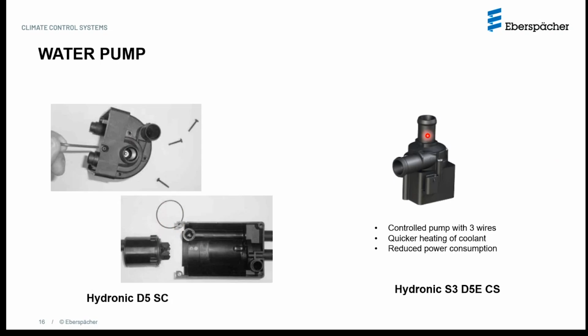Unfortunately, the coolant pumps on the Hydronic S3 are non-serviceable in the sense that you don't have any replacement part, especially the O-ring is not available as a replacement part. So in case you have a bad pump, which is highly unlikely, then you will have to replace the entire pump. These pumps are regulated as compared to the first generation. In the first generation, the pump would run at a constant speed, whereas in the third generation hydronic heaters, these coolant pumps can be regulated.